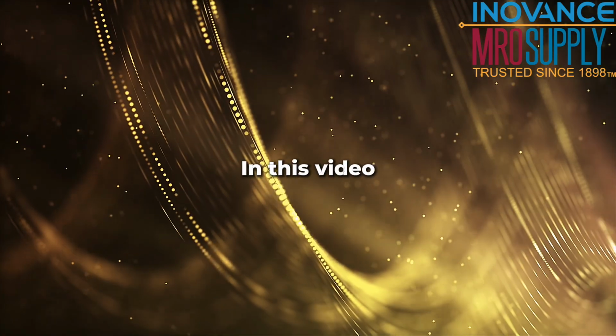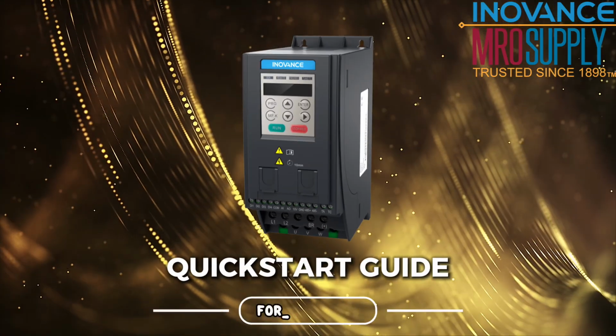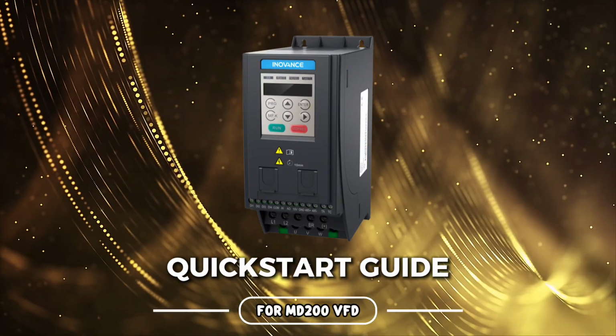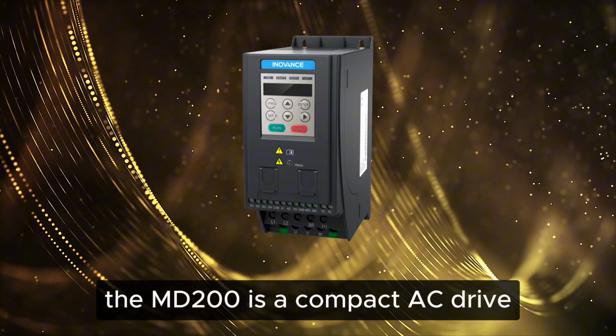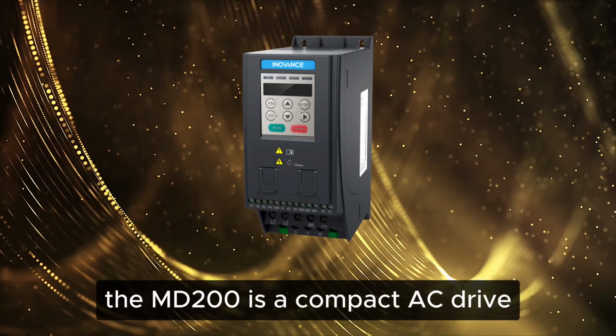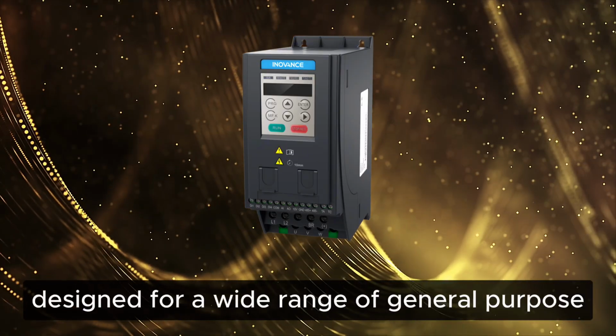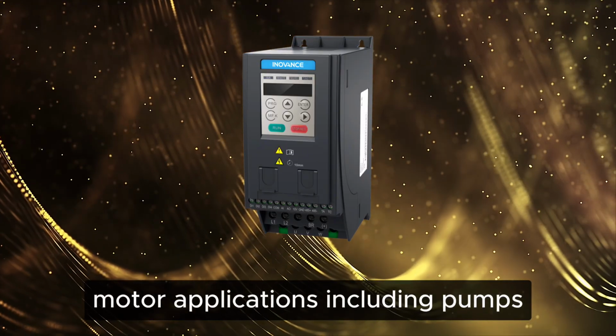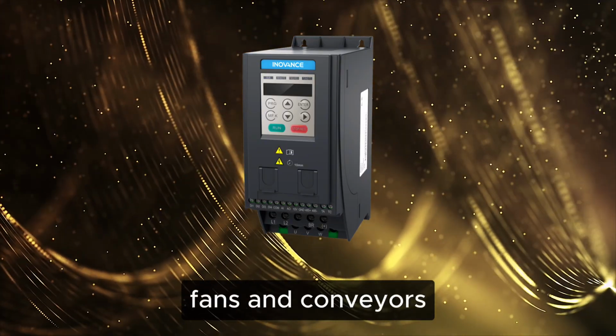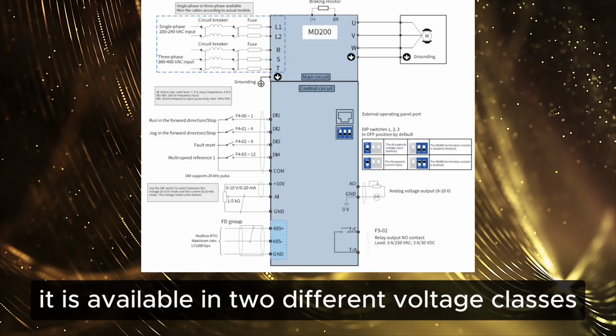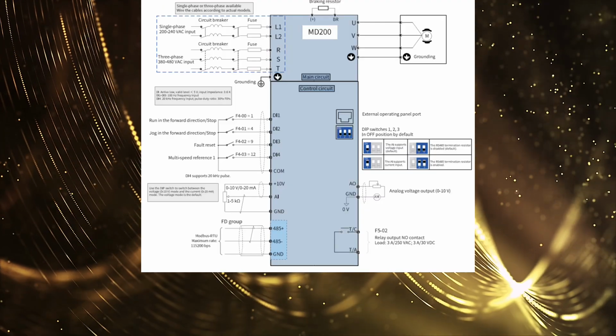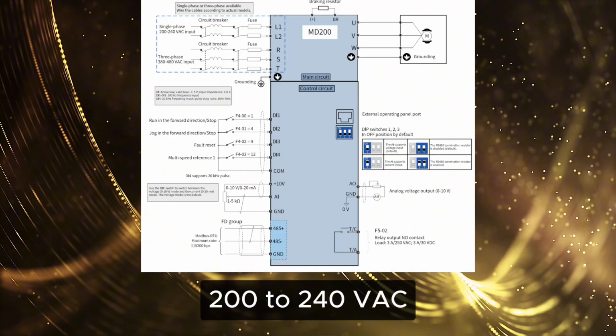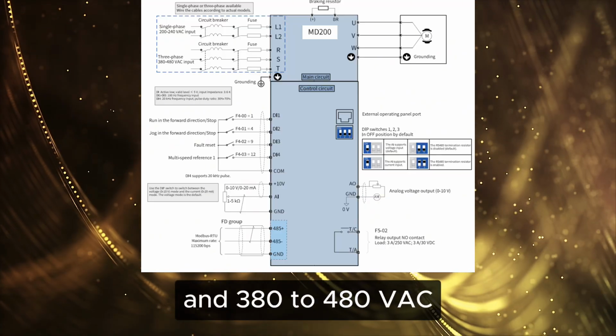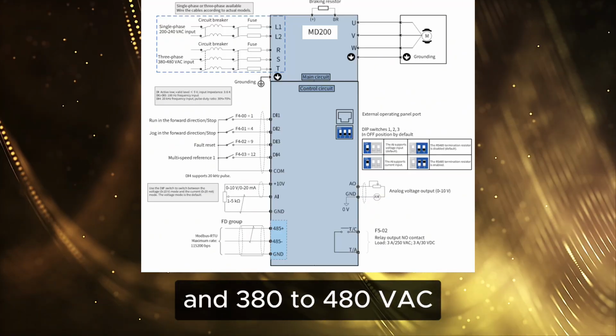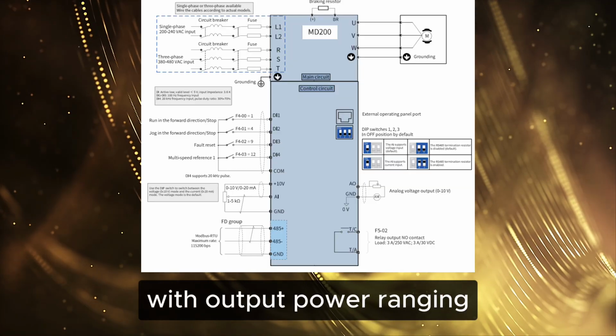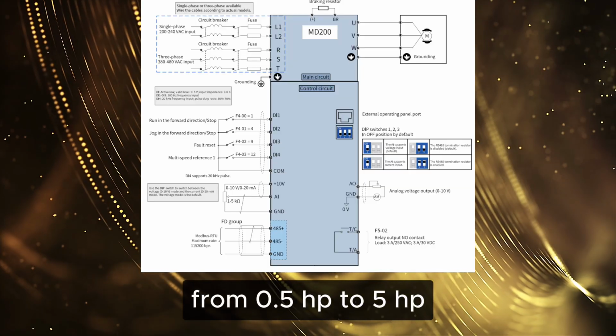In this video, we will be walking through a quick start guide for the MD200 VFD. The MD200 is a compact AC drive designed for a wide range of general-purpose motor applications, including pumps, fans, and conveyors. It is available in two different voltage classes, 200 to 240 volts alternating current, and 380 to 480 volts alternating current with output power ranging from 0.5 horsepower to 5 horsepower.